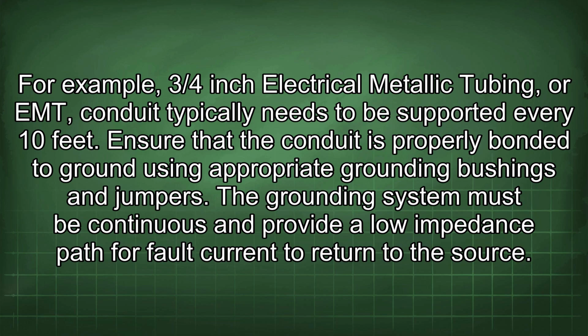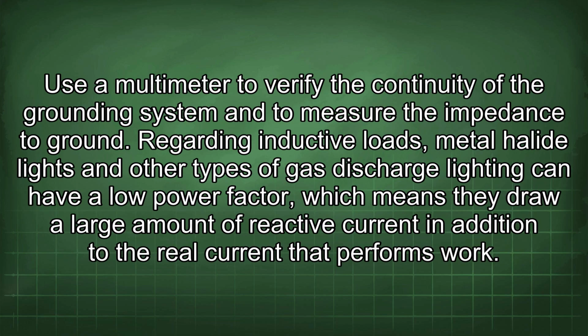Ensure that the conduit is properly bonded to ground using appropriate grounding bushings and jumpers. The grounding system must be continuous and provide a low impedance path for fault current to return to the source. Use a multimeter to verify the continuity of the grounding system and to measure the impedance to ground.